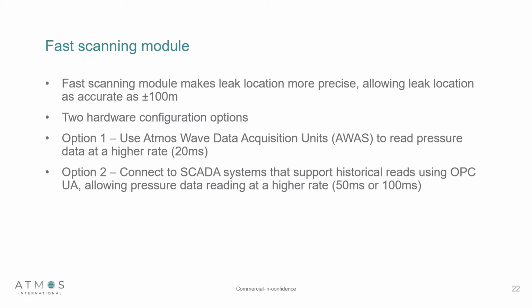Another method is to connect to SCADA systems that support historical reading using OPC UA. This will allow us to take that data when required and rerun it at a higher rate. So what we're saying is that the systems will still perform at the normal SCADA rate data that we're collecting, but when a leak event happens, the systems will request that data again at a higher acquisition rate. The system will request a section of data, and that section of data will be reprocessed at a higher acquisition rate, allowing us to dramatically improve our leak location.